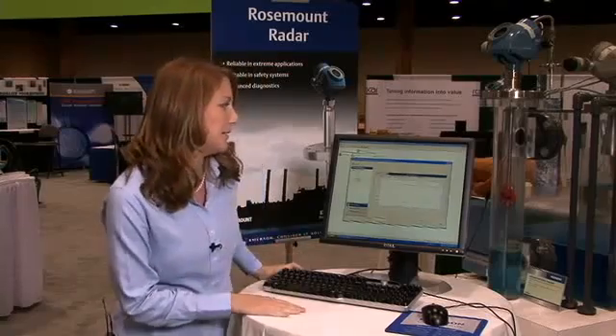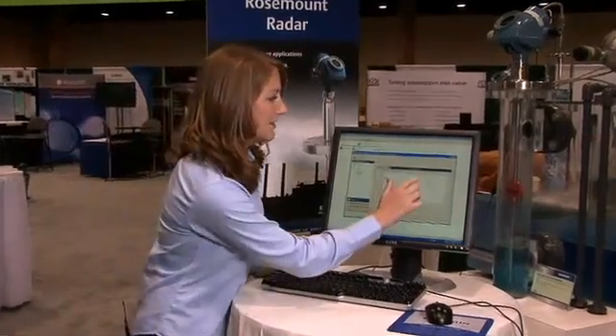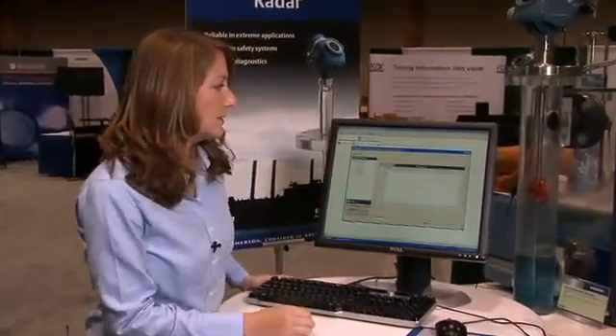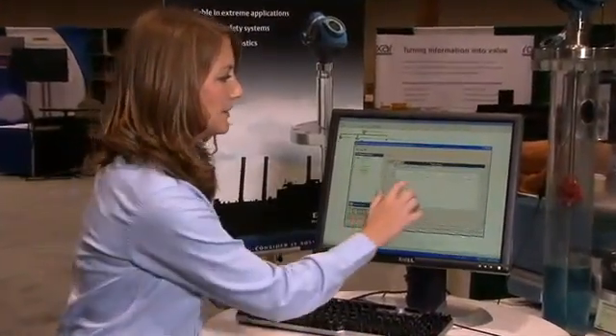So now I'm going to show you an echo curve here and as you can see this is the echo, the surface pulse and it is above this threshold here.